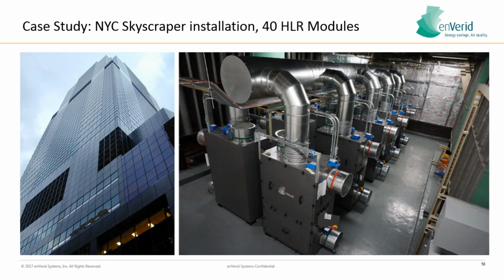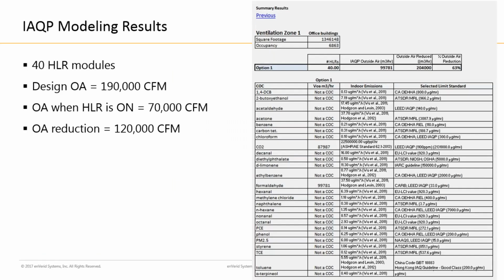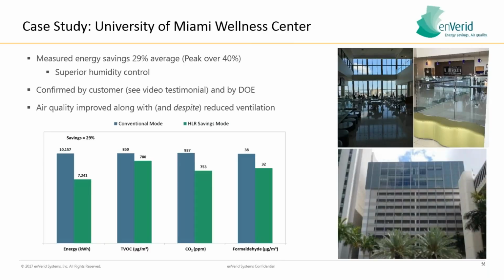The singular duct here that you see at the top, the purpose of that is for the exhaust cycle. Since it's a 24/7 application, we always have 2 units going into regeneration and the remaining units scrubbing the building. So you can see here that this solution can really scale up. And the net result on this was less than a 1-year payback. We reduced outside air 63% from 190,000 to 70,000 CFM for 7,000 occupants and 1.3 million square feet.